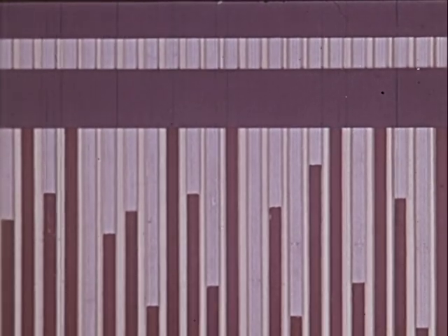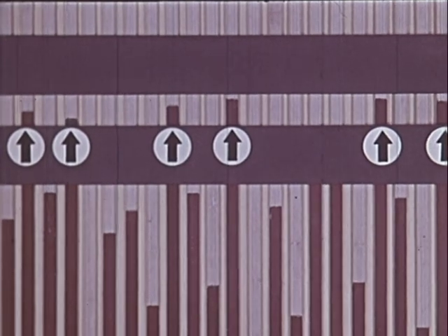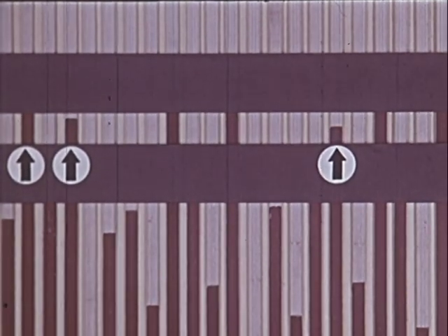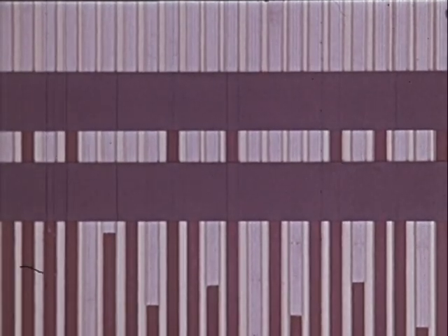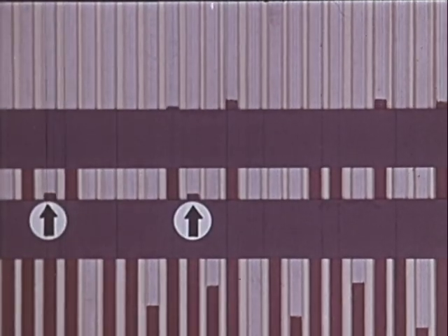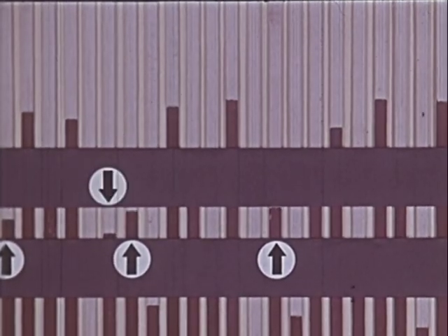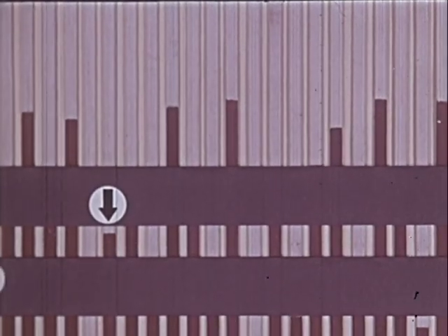To explain the functioning of a single-channel spectrometer, we represent the pulses registered by the scintillation detector by straight lines. The height of each pulse depends on the energy of the gamma quantum which initiated the pulse. Each isotope is characterized by a typical energy distribution. That means that quanta are emitted only at distinct energies. Therefore, pulses of certain heights occur most frequently. Here, the measuring channel of the discriminator is represented by a slit through which we look at the pulse spectrum. Only those pulses come in for counting, the height of which corresponds with the position of the slit.